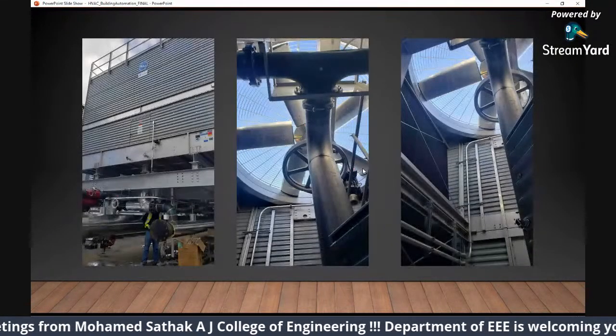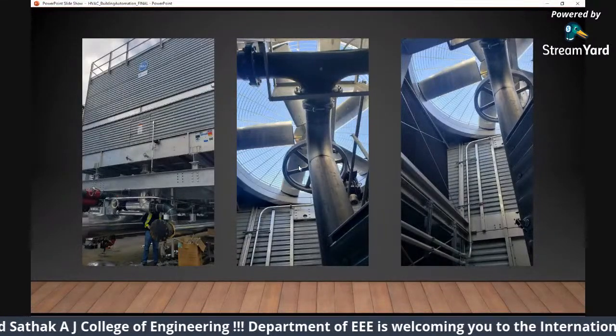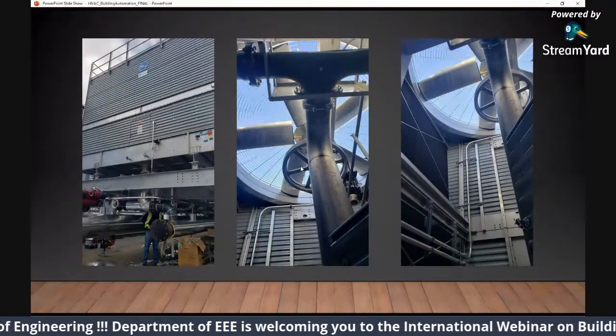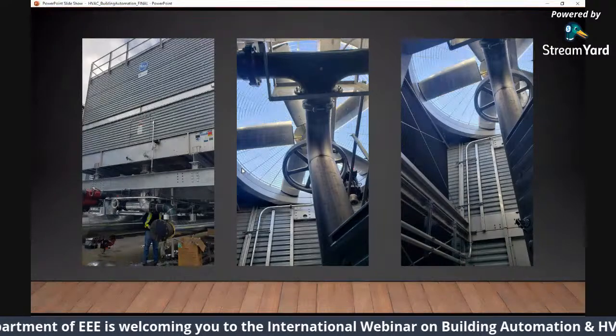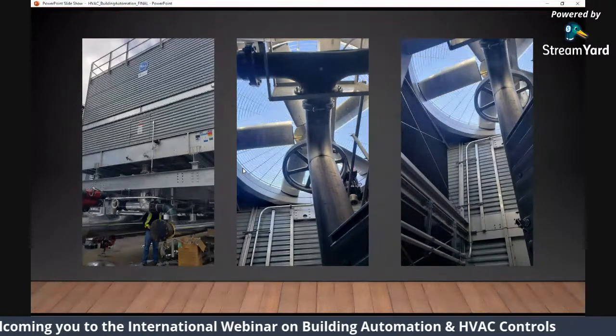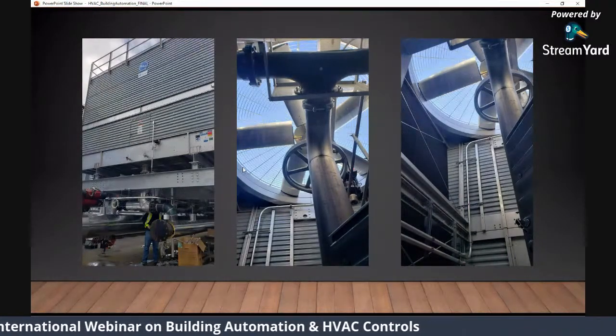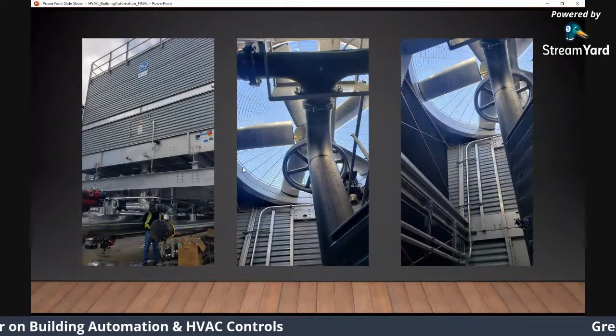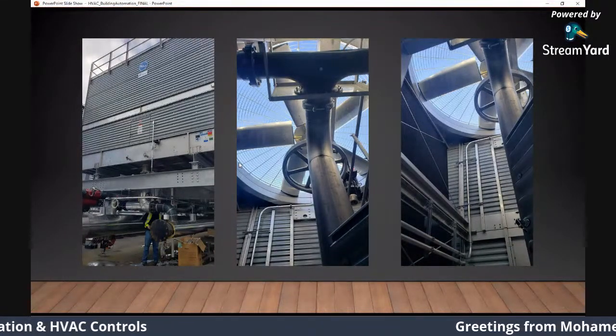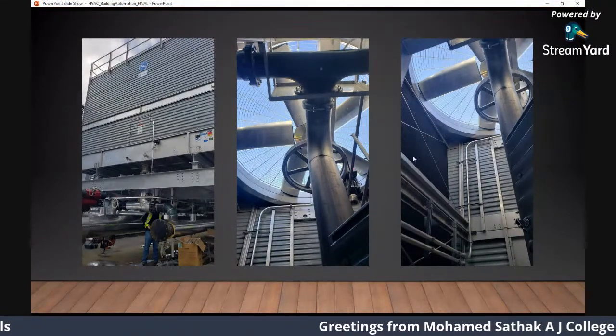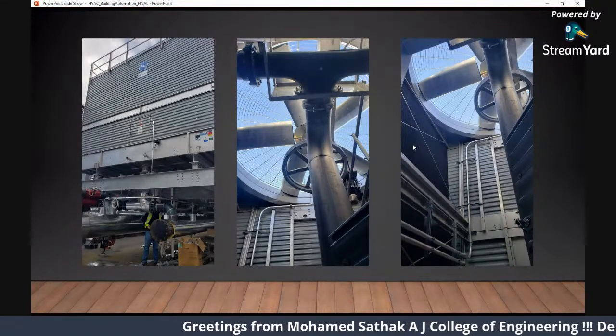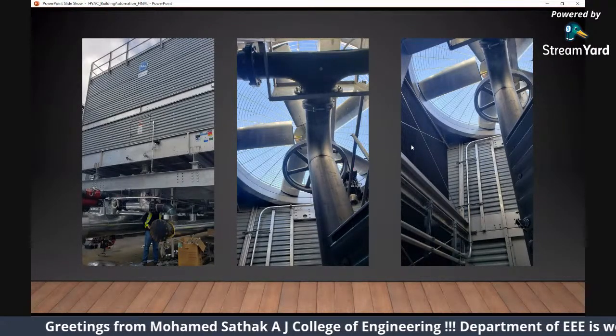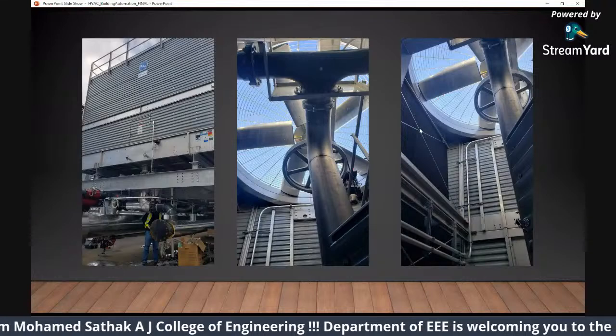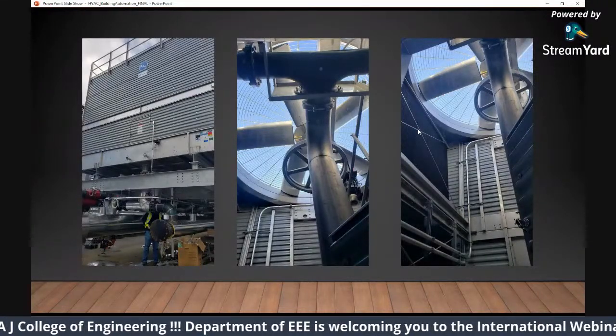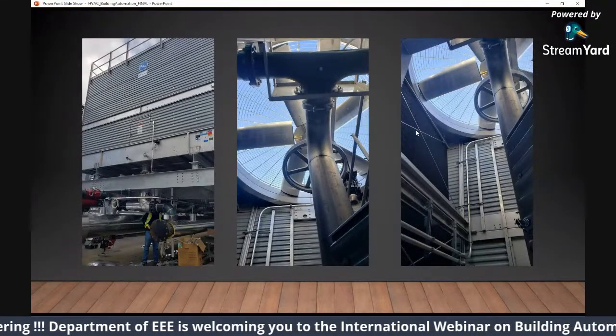All right. And I'll show the real pictures. So again, this is your cooling tower. I'll try to bring in the pictures from your left. Go from the left. So that big box is called your cooling tower. What is inside is a big fan. That's your cooling tower fan, which keeps rotating all the time. And if you can see on the left in the third picture, the black thing, that's called the coil. That's where your water gets poured on the sides. And when you keep rotating the fan, with the evaporative cooling method, your water gets cooled.